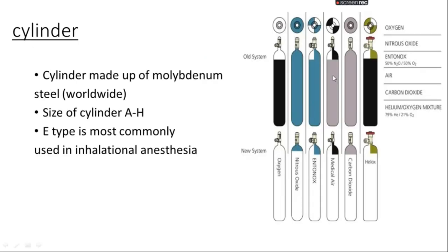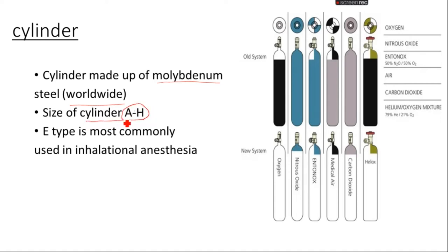If we talk about the cylinders most commonly used, what are they made of? They are made of molybdenum steel. Molybdenum steel is used worldwide and in many countries as the cylinder material. The sizes of the cylinders range from A to H, where A is very small and H is very large. The size most commonly used in inhalational anesthesia is E-type.